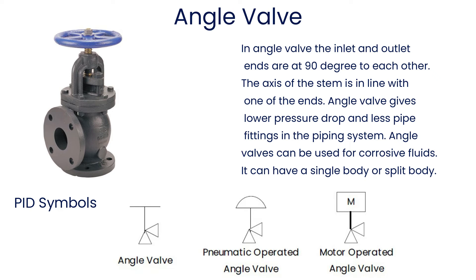In an angle valve, the inlet and outlet ends are at 90 degrees to each other. The axis of the stem is in line with one of the ends. Angle valve gives lower pressure drop and less pipe fittings in the piping system. Angle valves can be used for corrosive fluids and can have a single body or split body.